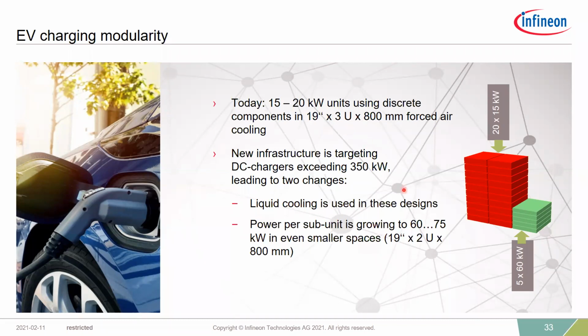Now, because of increasing DC charger ratings and increasing pressure to reduce the cost of charging, they are moving to higher power charging, like each rack at 60 kilowatt. This way, by just plugging in 5 units of 60 kilowatt, you can reach 300 kilowatt. See how many units you can bring down, and with a smaller space you can place 300 kilowatt. This also reduces the space needed.